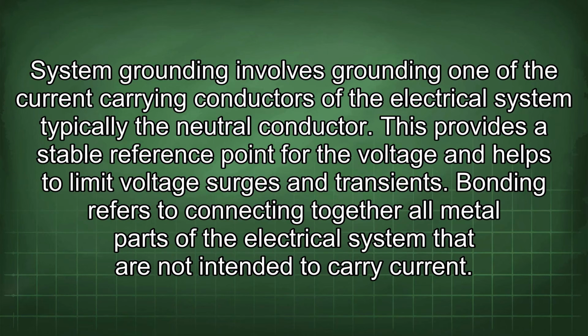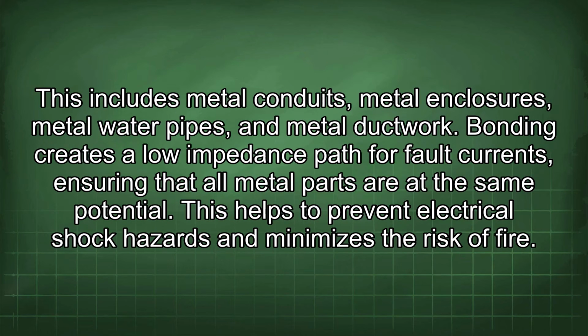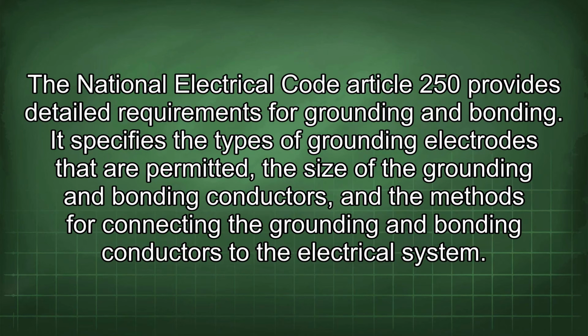Bonding refers to connecting together all metal parts of the electrical system that are not intended to carry current. This includes metal conduits, metal enclosures, metal water pipes, and metal ductwork. Bonding creates a low impedance path for fault currents, ensuring that all metal parts are at the same potential. This helps to prevent electrical shock hazards and minimizes the risk of fire. The National Electrical Code Article 250 provides detailed requirements for grounding and bonding. It specifies the types of grounding electrodes that are permitted, the size of the grounding and bonding conductors, and the methods for connecting the grounding and bonding conductors to the electrical system.